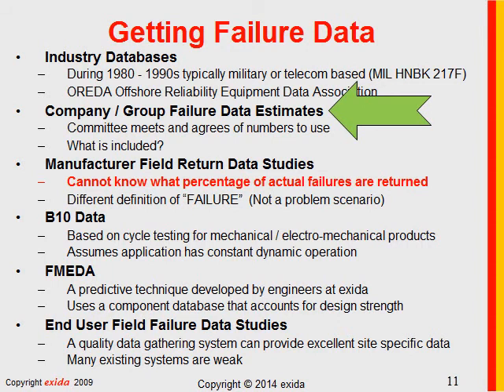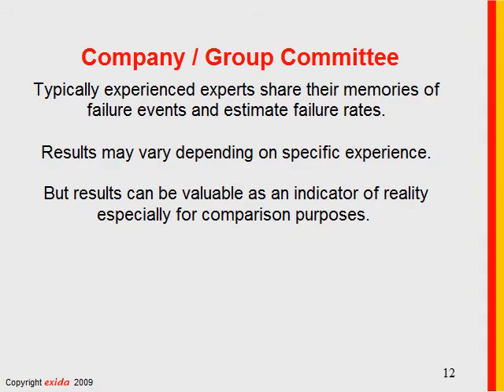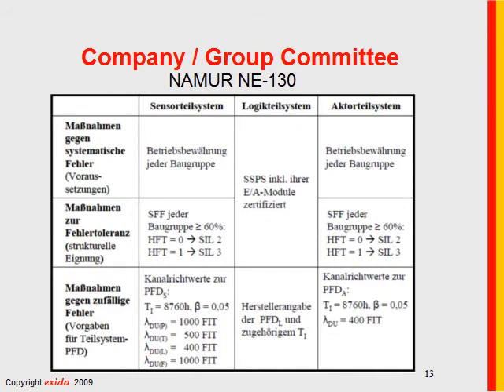Company and group failure rate data estimates typically involve experienced engineers sharing their memories of failure events to estimate failure rates. It's not a scientific approach, and results vary depending on who's in the room, but the results can be valuable, especially for comparison purposes. For example, a committee in Germany from the German Chemical Industry Group published NE130, where they published failure rates for sensors, logic solvers, and final elements — including a dangerous undetected failure rate for a final element assembly of 400 FITs.